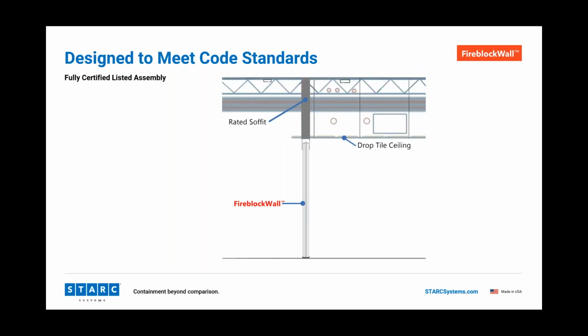And just to show you, typically to meet NFPA 241 standards or certainly the E119 standard, a rated firewall must be constructed up against an equivalent 1 hour rated assembly, which is typically, in this case, a hard soffit from floor to the deck above. Nominally, to meet this requirement with our system, the customer would build this soffit down from the deck to the ceiling plane. Then our system is installed under the hard soffit to create the fire rated assembly. Alternatively, a supported shaft wall lid assembly can be constructed under the ceiling from the rated wall out, and our system could be installed underneath that lid.